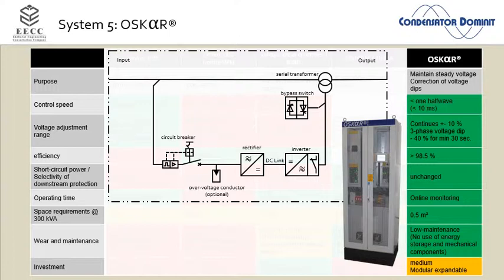In that case, I must do one thing. I must bypass my transformer here as fast as possible. That was a challenge. To make the bypass fast was much more complicated than to make the reaction time fast. But what we do, if we detect a jump in current on that side into the short circuit range, we first use the IGBT inverter to bypass the system. We basically take the 3 bottom IGBTs and make them open, and the top one close.